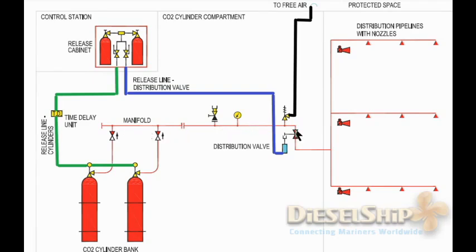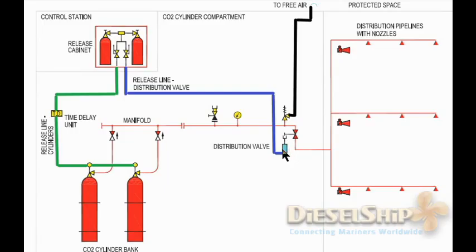On modern ships there is a pressure switch on the manifold. When there is a small leak or some pressure in the line, it detects the pressure and gives an alarm — either a CO2 leak alarm or a CO2 release alarm. The pressure switch can be calibrated, for example 1 to 10 bar as leak alarm and above 10 bar as release alarm, depending on the ship's automation system. After that, the distribution valve is operated through a piston — pushing the piston up opens the valve and the CO2 goes to the engine room.